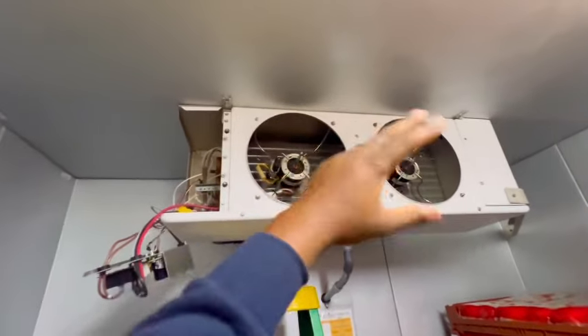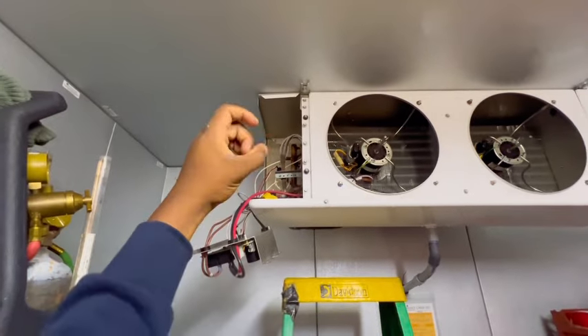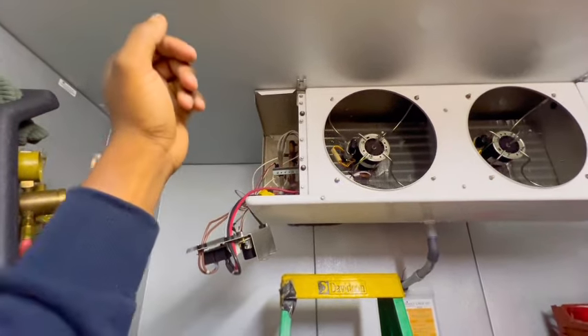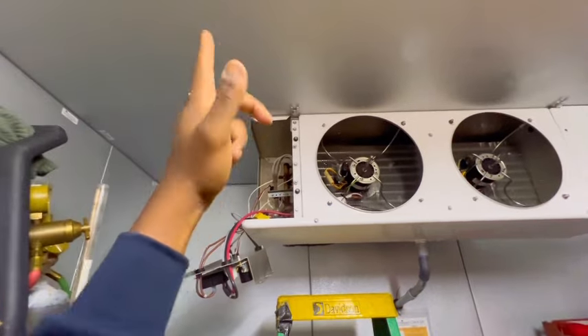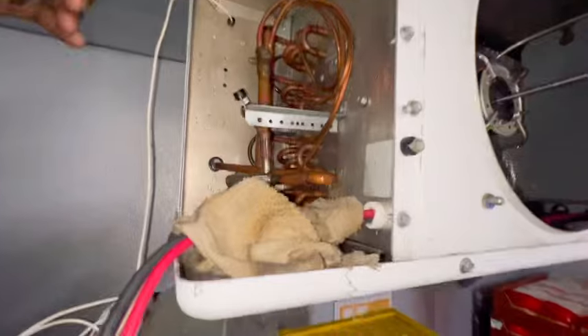I got the coil nice and clear all around. I had used my magnet tool — the manual tool — to open it up because it wouldn't even open up at all. Right now I'm gonna go up top, pump it down, and then get this valve out.